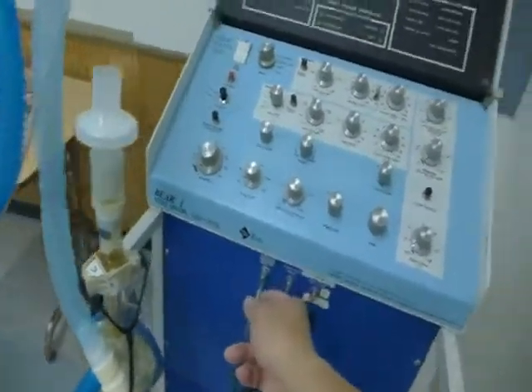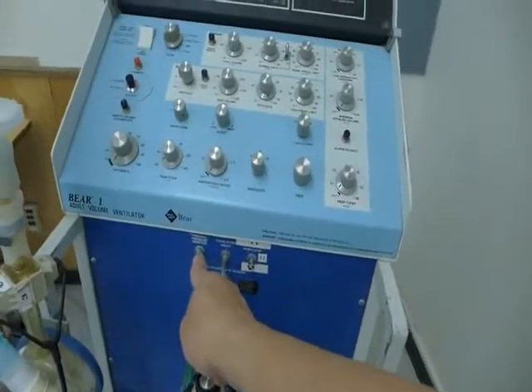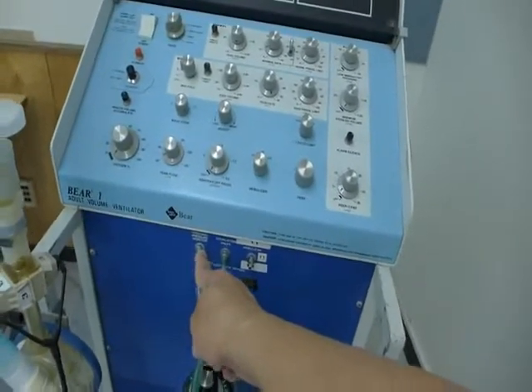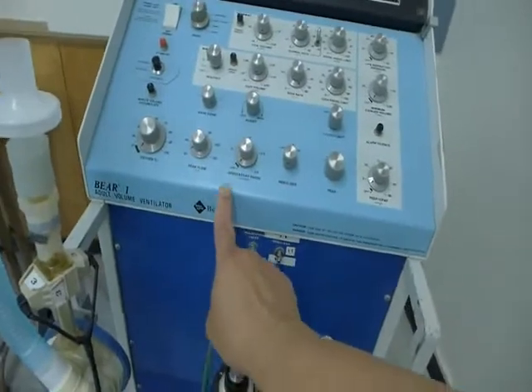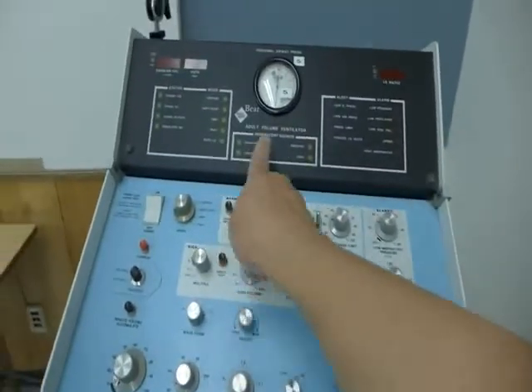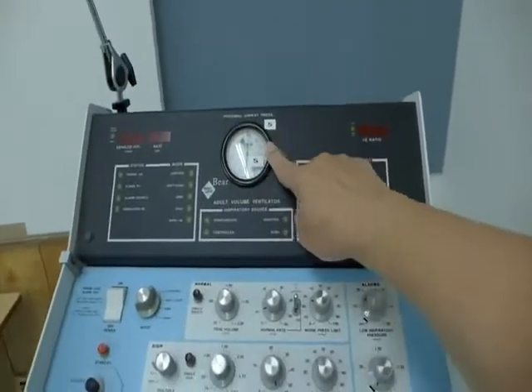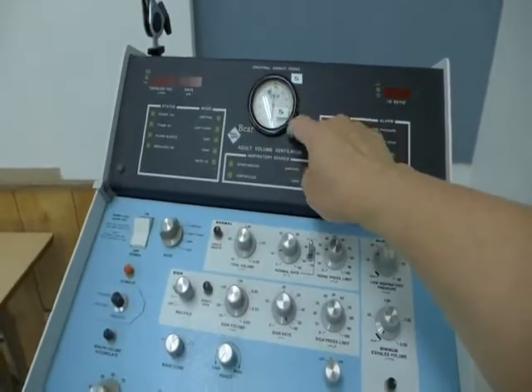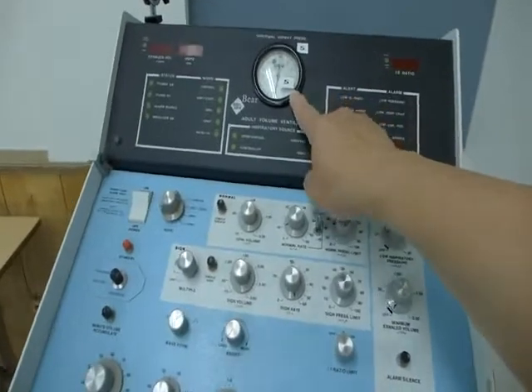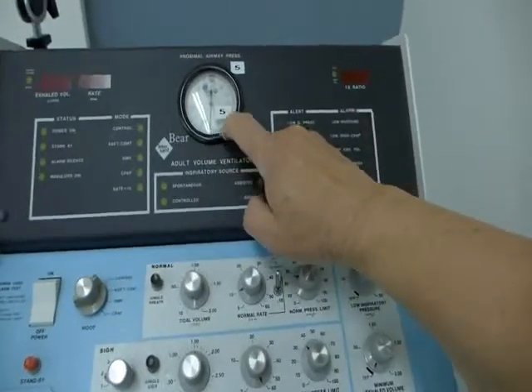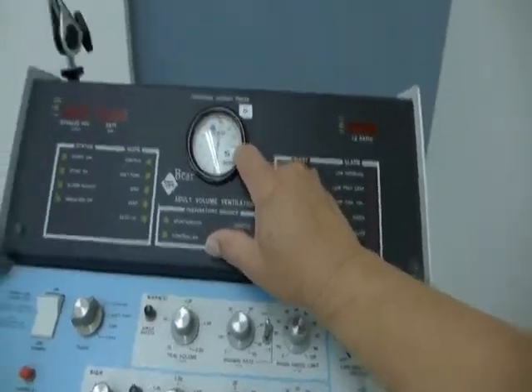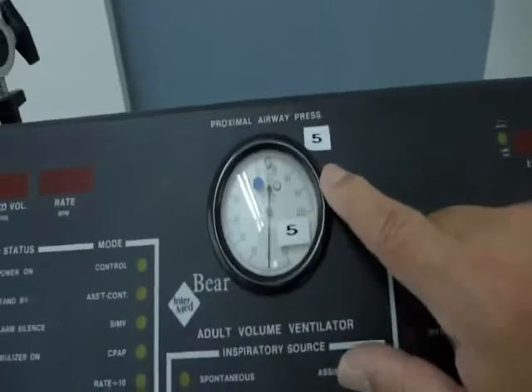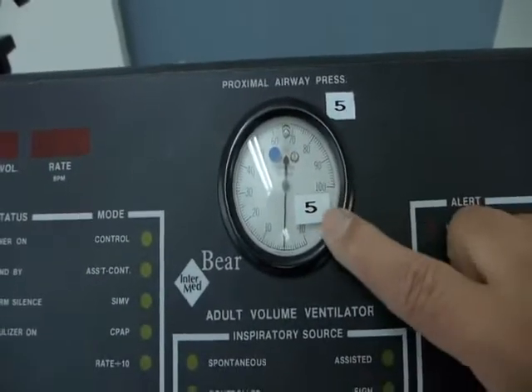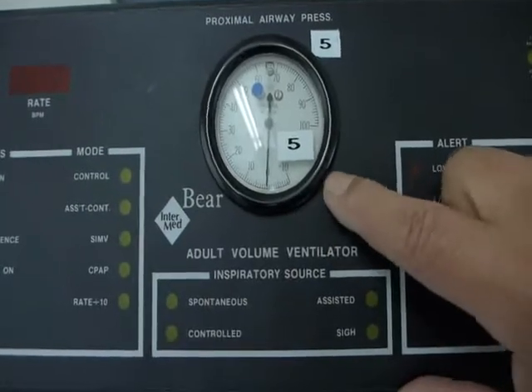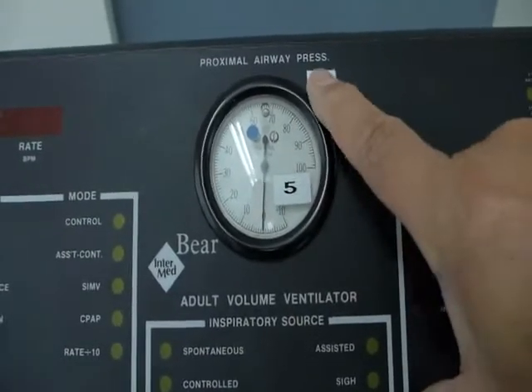All right, and also at the front here we have the proximal pressure monitor. Basically, in the back it has tubing connected all the way to the proximal airway pressure gauge. This is the analog gauge. It has a range from -10 to plus 100. This is number 5 over here. It's called proximal airway pressure.